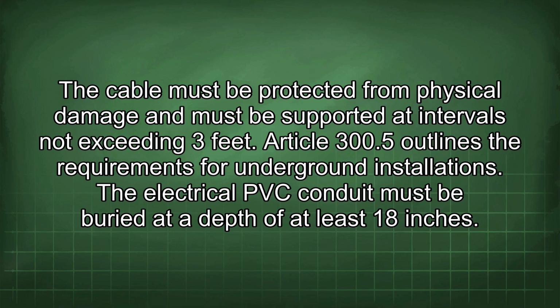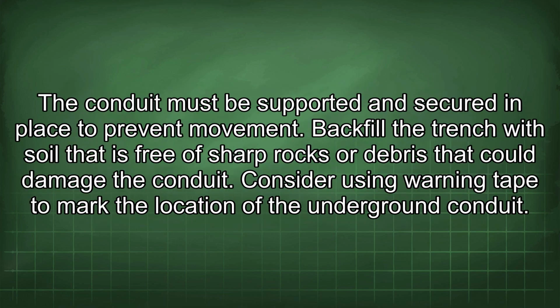Article 300.5 outlines the requirements for underground installations. The electrical PVC conduit must be buried at a depth of at least 18 inches. The conduit must be supported and secured in place to prevent movement. Backfill the trench with soil that is free of sharp rocks or debris that could damage the conduit. Consider using warning tape to mark the location of the underground conduit.